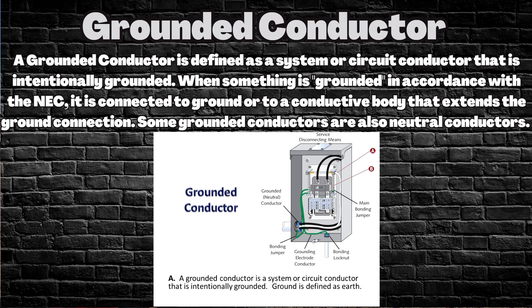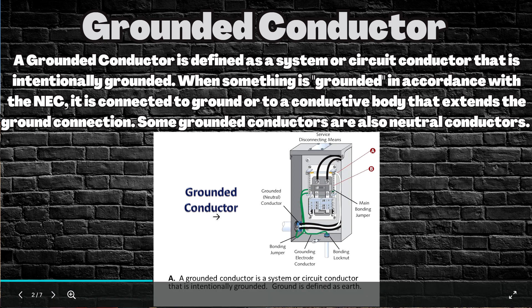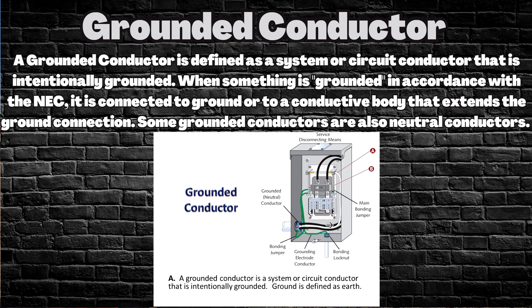First, let's talk about the grounded conductor. A grounded conductor is defined as a system or circuit conductor that is intentionally grounded. When something is grounded in accordance with the NEC, it is connected to ground or to a conductive body that extends the ground connection. Ground is defined as earth. Some grounded conductors are also neutral conductors.